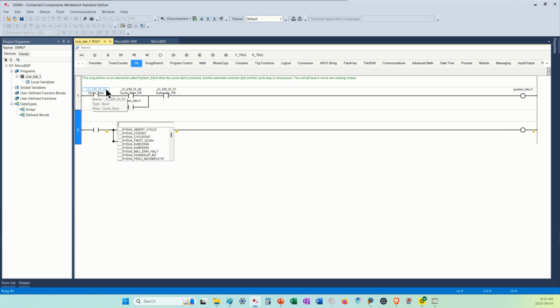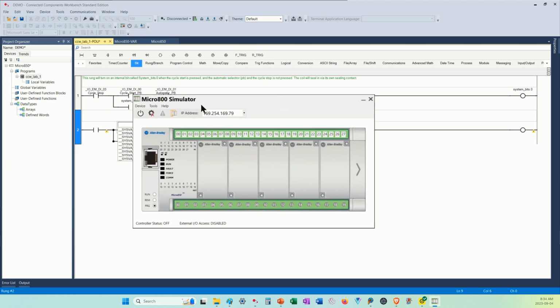addresses. So an address is the identification of a logic location that is physically connected to a real-world input or output, whereas a variable is an internal address. So this I can say, and I can go and find that particular digital input screw terminal. Okay, so that's digital input 3, and if this was the actual PLC above it, there would be literally the terminal screw with the wire attached to it. And I would say, okay, there it is. I can trace the wire to the actual device.